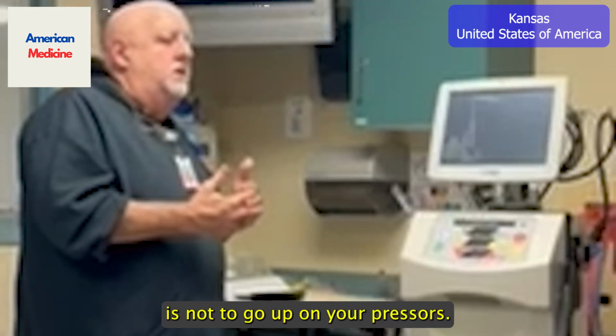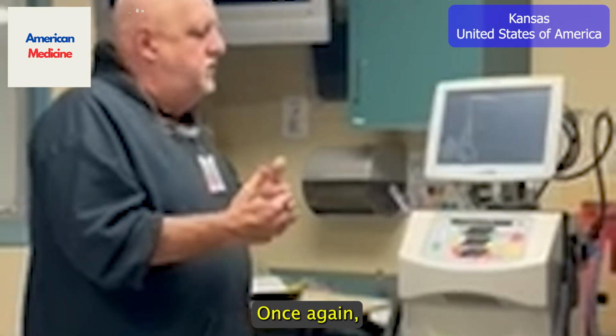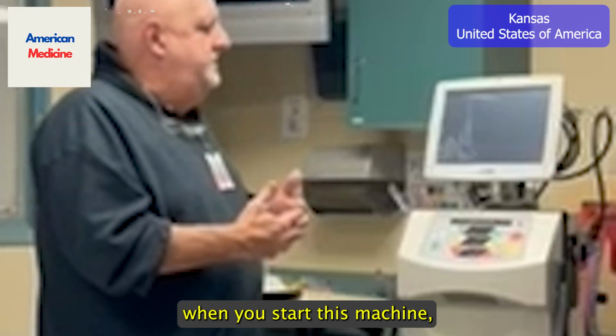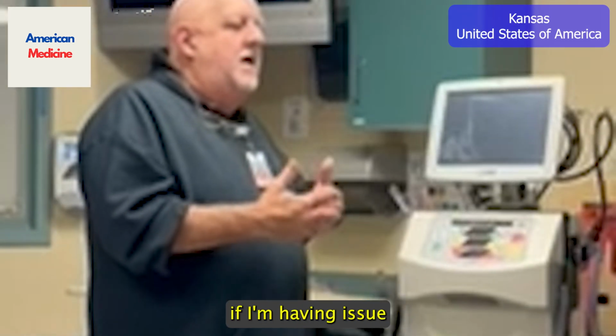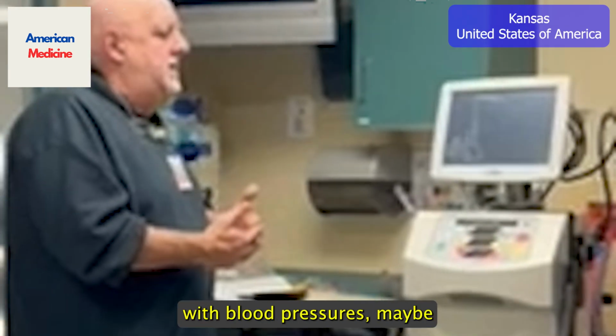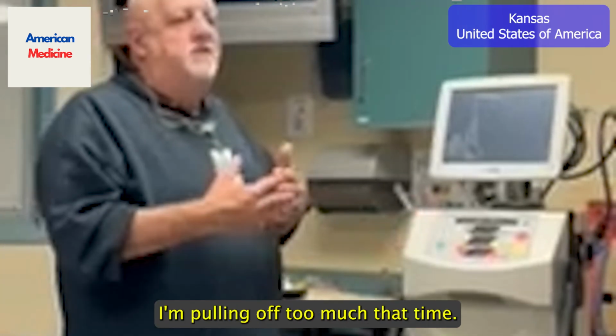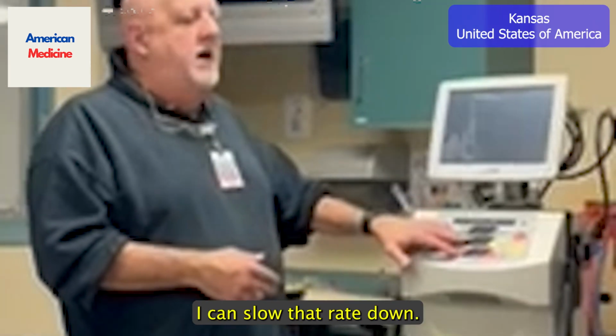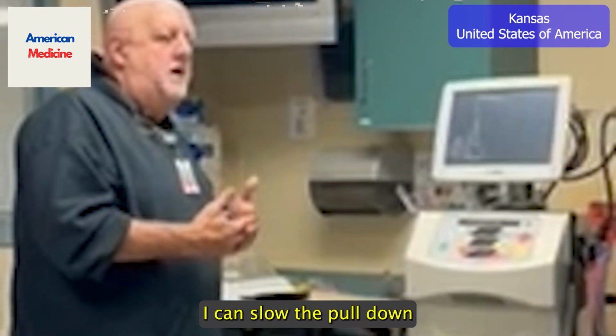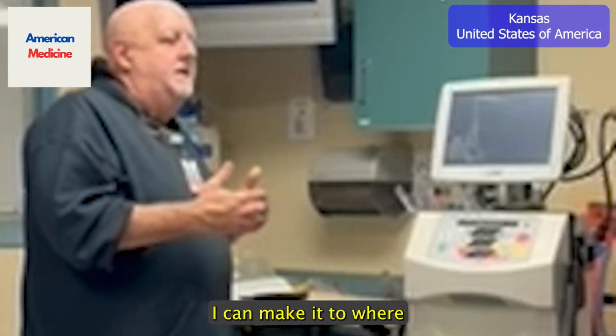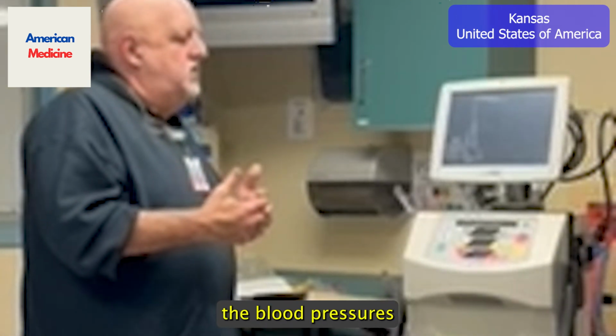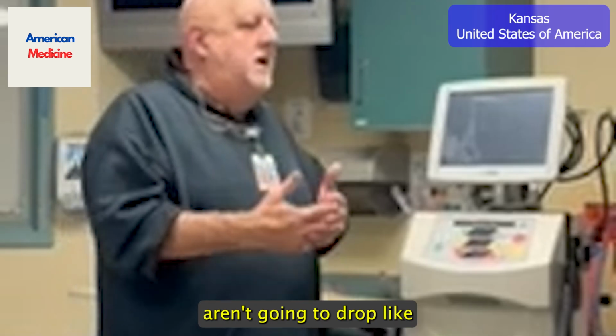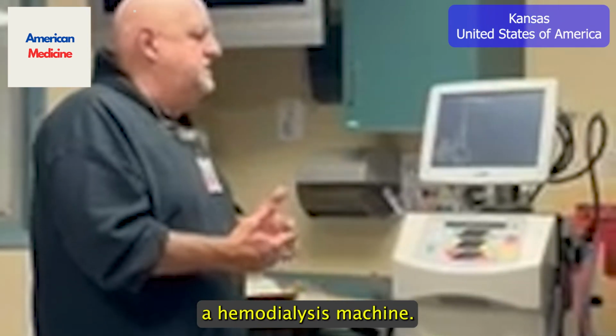Your ultimate goal is not to go up on your pressors. Once again, when you start this machine, if I'm having an issue with blood pressures, maybe I'm pulling off too much at that time, I can slow that rate down. I can slow the pull down on that patient. I can make it to where the blood pressures aren't going to drop like they normally would on a hemodialysis machine.